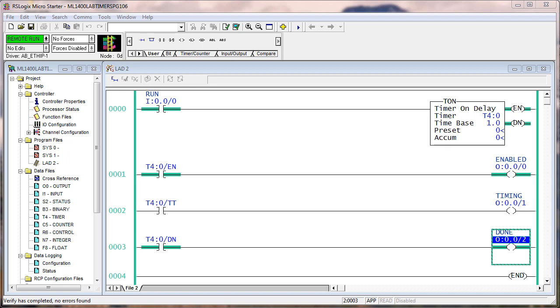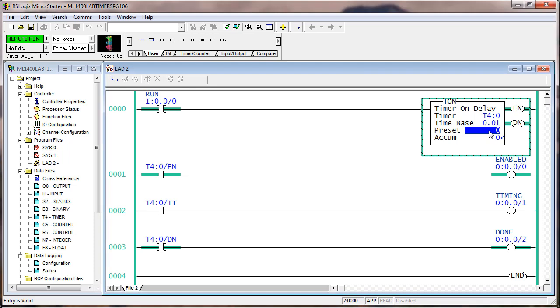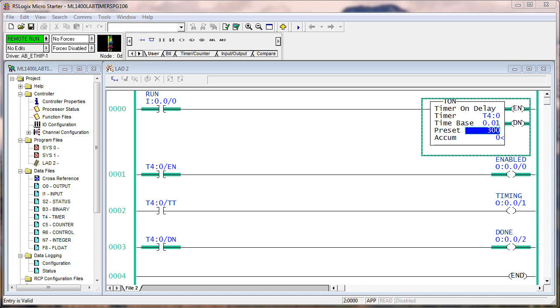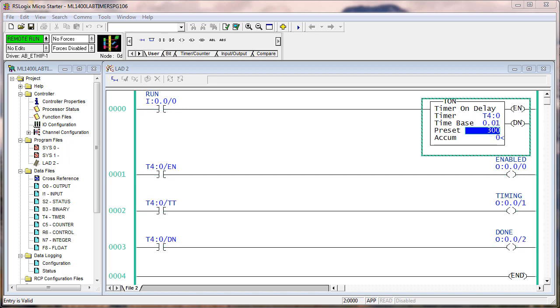Then I had you change the time base to a hundredth of a second. To do that you had to put it in edit mode and put in a preset of 300, which in hundredths of a second would be three seconds. I had you switch the input back off because that resets the timer. Notice all the bits are off now. Then I had you turn on input zero, and when output two energizes, flip the selector switch back to the off position. When it accumulates to three seconds, it's done.